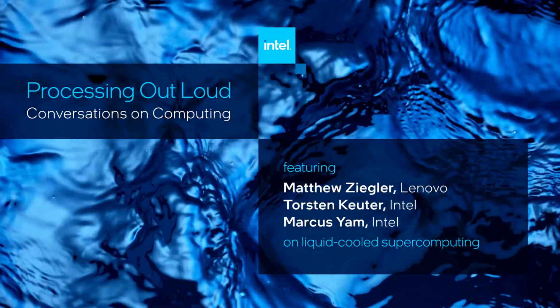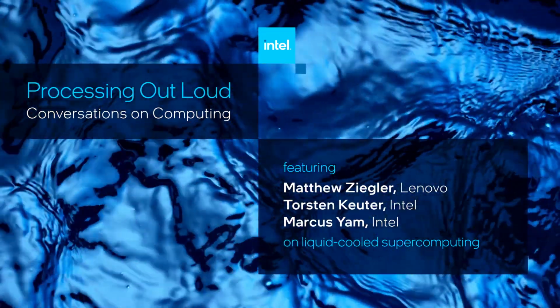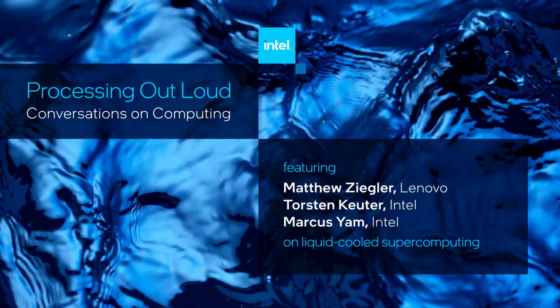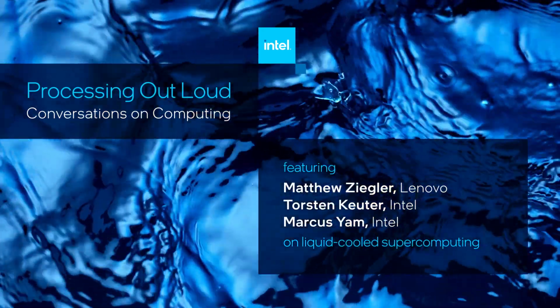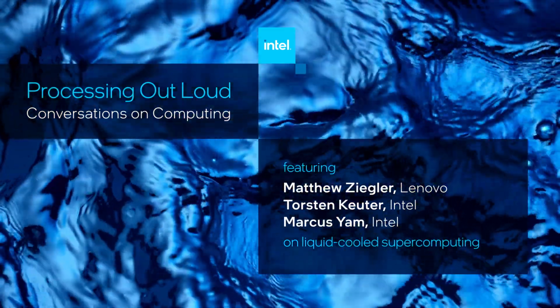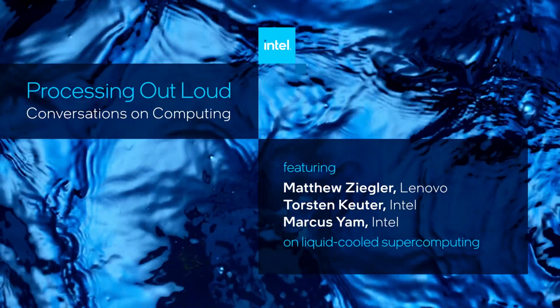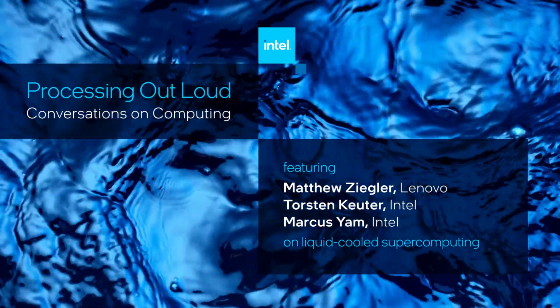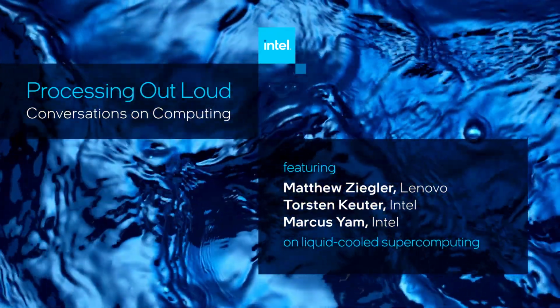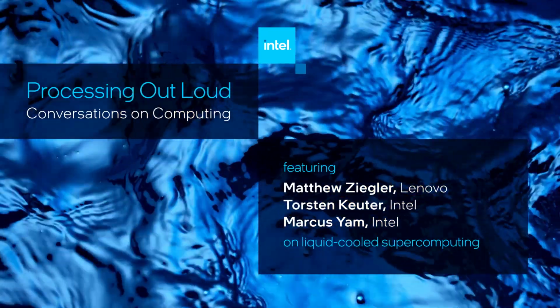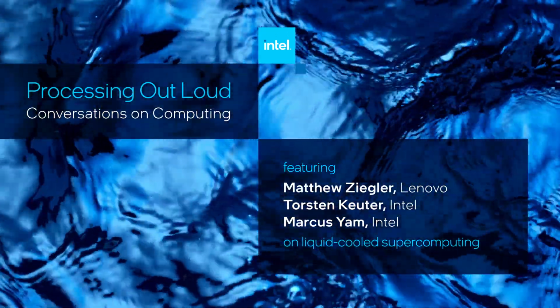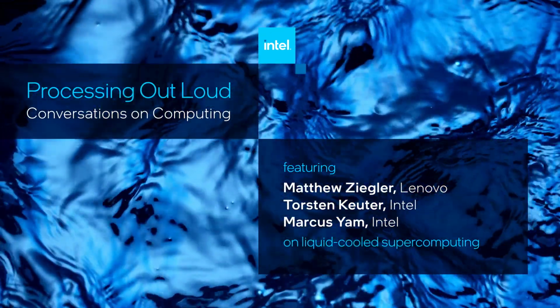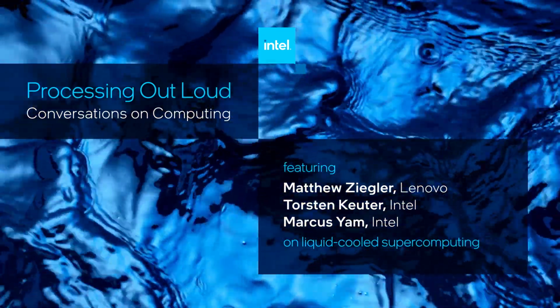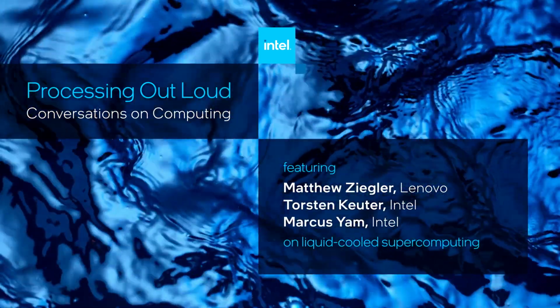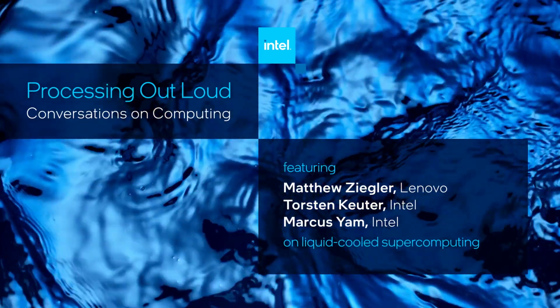With liquid cooling, we can stay so far below that threshold for throttling that you can continue to run at the highest frequency possible. So if the spec sheet says the turbo frequency is 3.1, you can actually run at that 100% of the time, for the most part, if you're running liquid through it at nominal temperatures. That's another benefit of liquid cooling—the performance aspect.